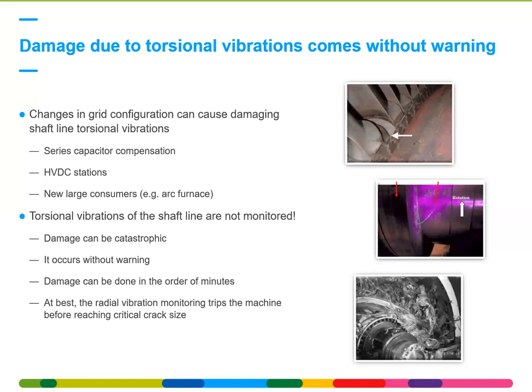And if it happens, you can see some examples on the right. For instance, you can have a rotor cracking. So the middle picture where you have crack initiation at a fillet transition of a larger diameter to a smaller diameter, typically near couplings. The figure below is retaining ring failure, which is also the cause of torsional vibration, where you have actually fretting fatigue of the shrink fit surface of the retaining rings with respect to the generator rotor.